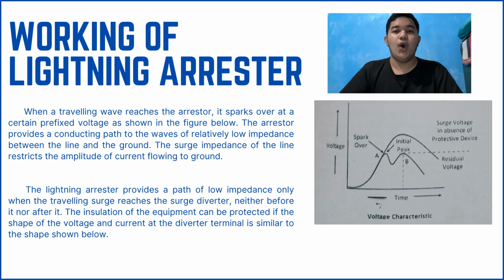And here's the smart part. The lightning arrestor only conducts when a surge occurs, not before and not after. Under normal conditions, it stays inactive, allowing regular current to pass through the system uninterrupted. The shape of the voltage and current across the arrestor ensures that the connected equipment remains safe even during high-energy lightning events. So the next time you see a lightning flash across the sky, remember, deep inside every substation, a lightning arrestor is standing guard, silently protecting our power system from nature's fury. And it's not just a piece of equipment, it's the unsung hero of electrical safety.